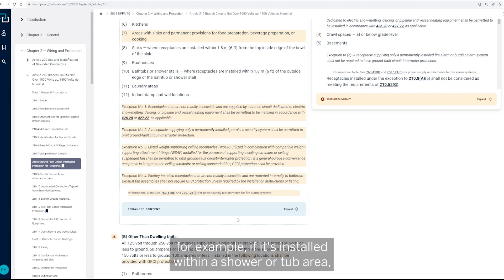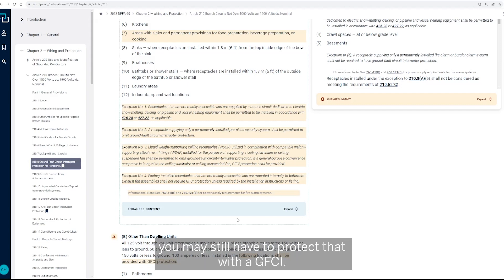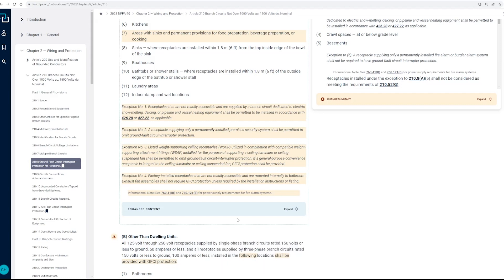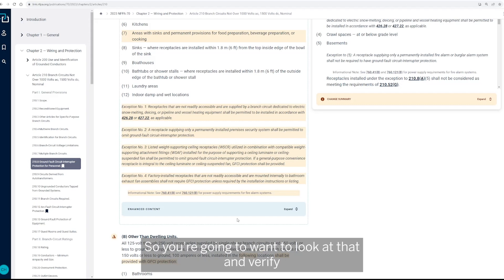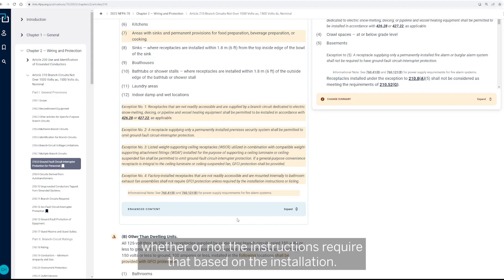So where it's physically installed within that bathroom may require that. For example, if it's installed within a shower or tub area, you may still have to protect that with a GFCI in that case, even though it's not readily accessible and it's internal to the bath fan. So you're going to want to look at that and verify whether or not the instructions require that based on the installation.